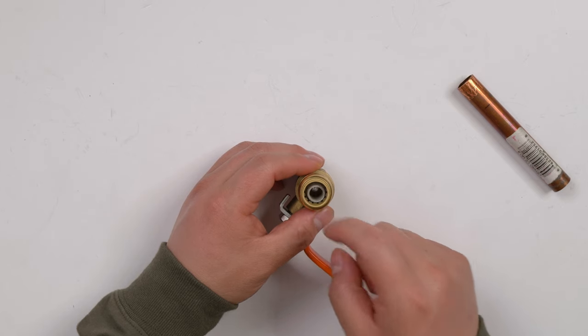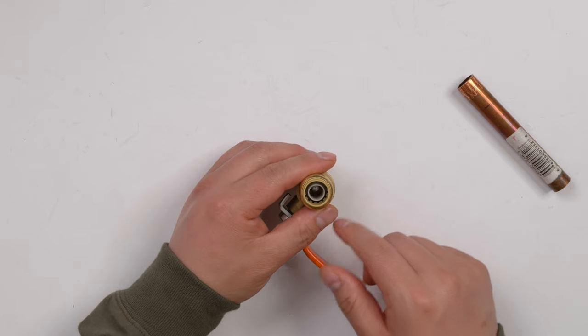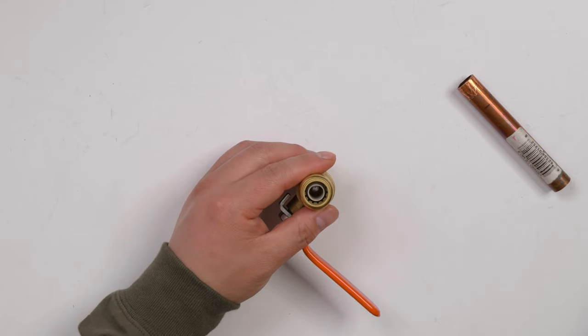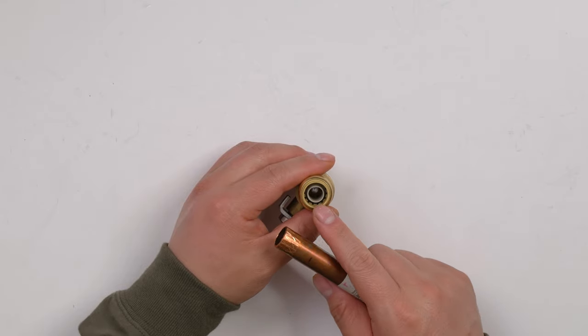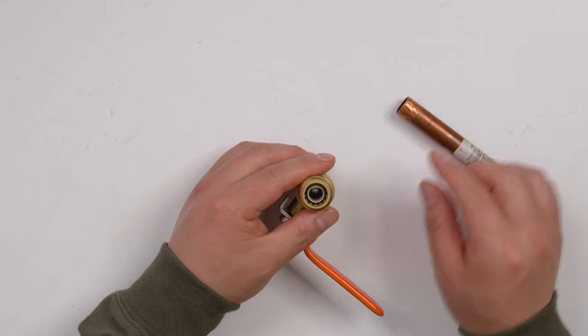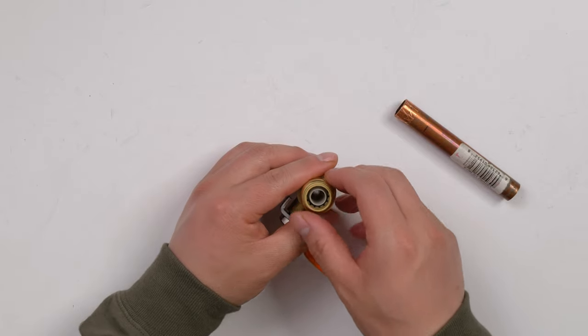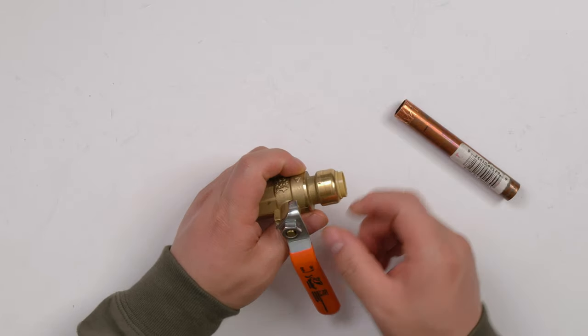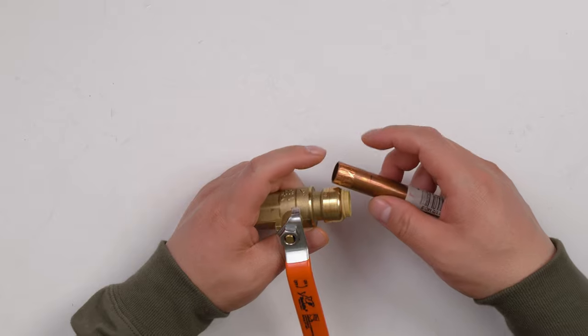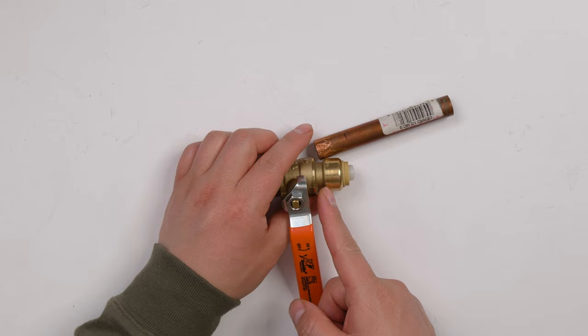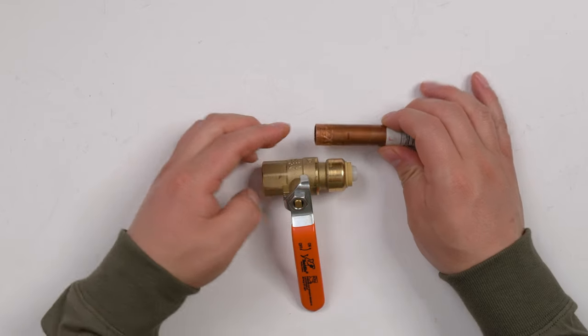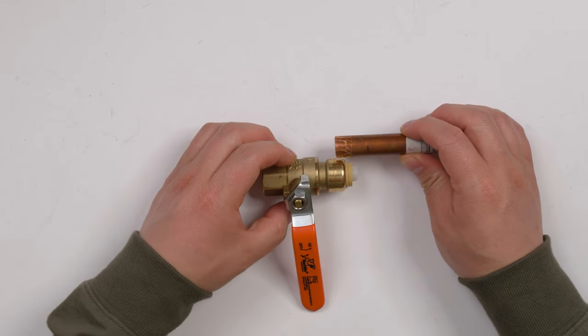Right in the middle there is a plastic tube. This is the stiffening collar. If you're using PEX, this one must be in there, but if you use copper it doesn't have to be—but you can leave it inside. You see the metal teeth? This is the stainless grab ring. It actually grabs the tube. And inside, right above here, there is the O-ring. The O-ring actually seals the tube.